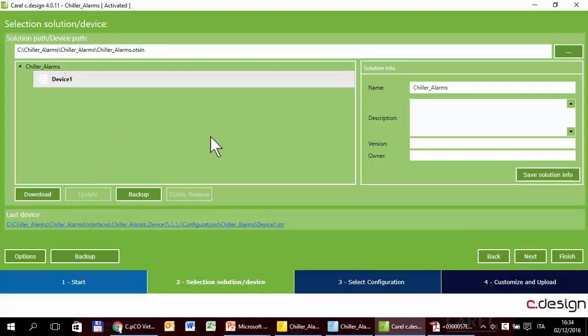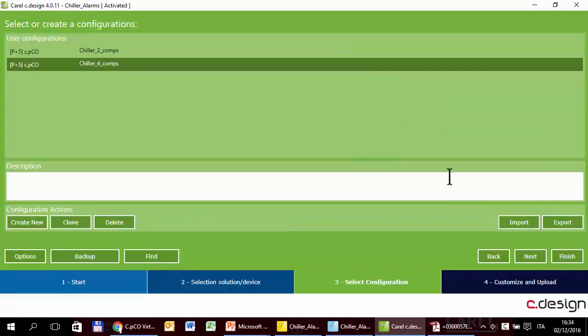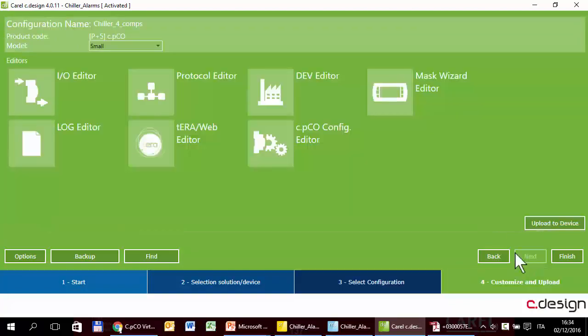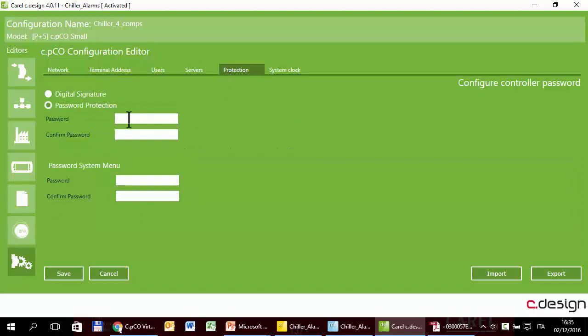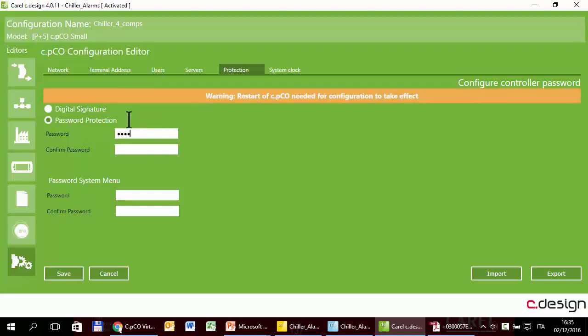Let's try it. Open the project, select the configuration we want to upload and protect — chiller 4 compressors. The protection is here in the c.pCO Configuration Editor. Here is the password — this is an eight-character alphanumeric password. I will insert a simple password: 1111.